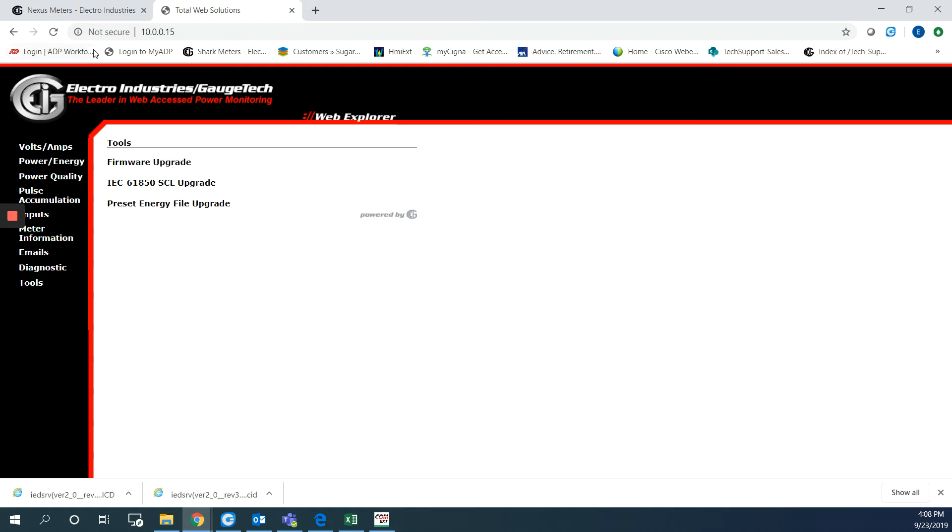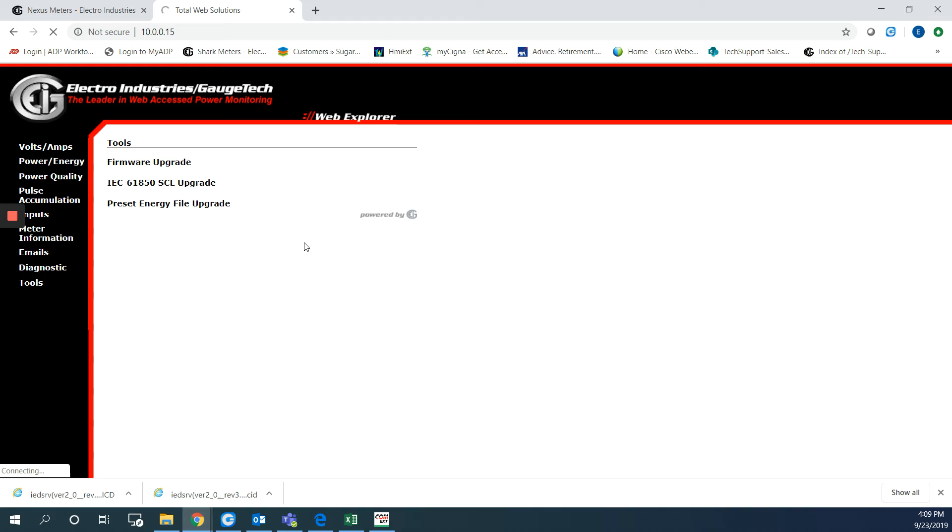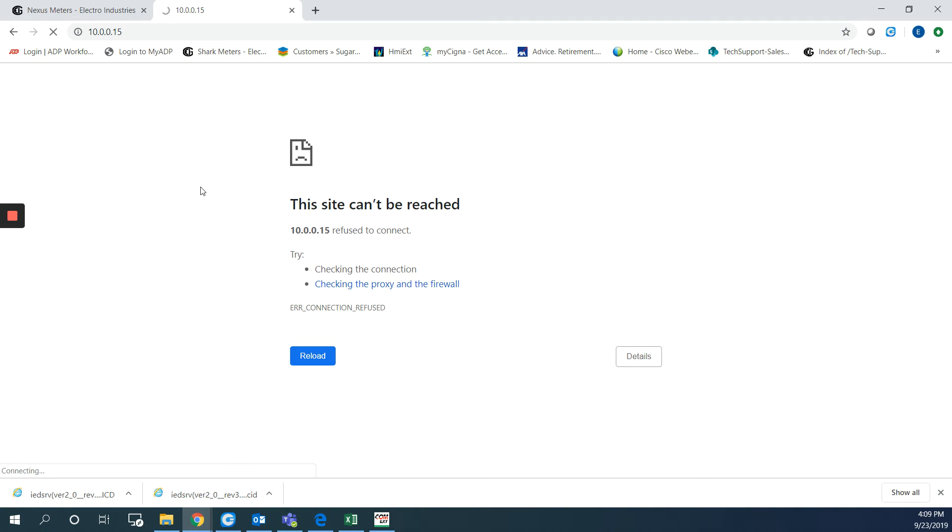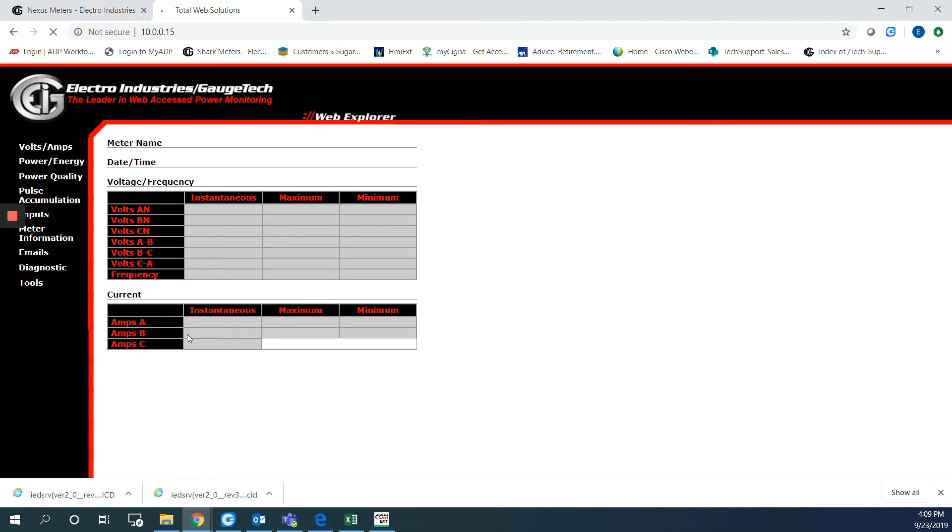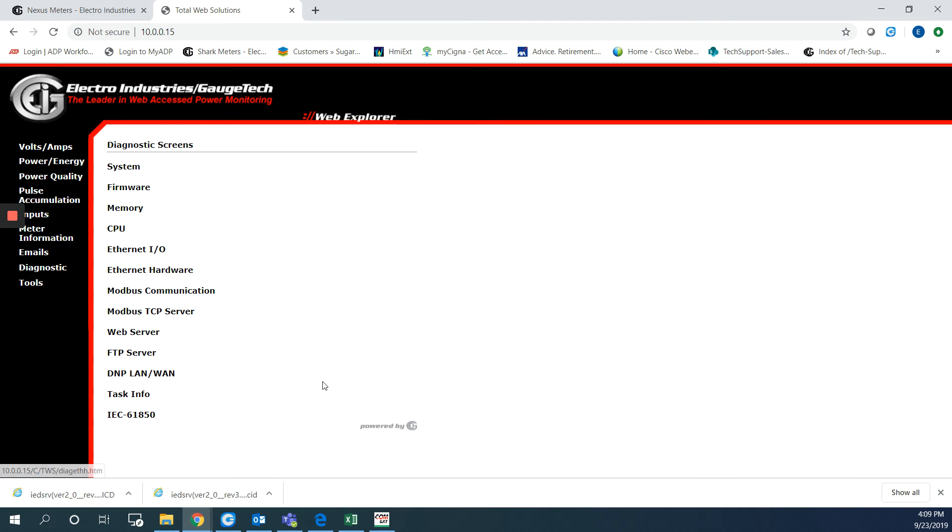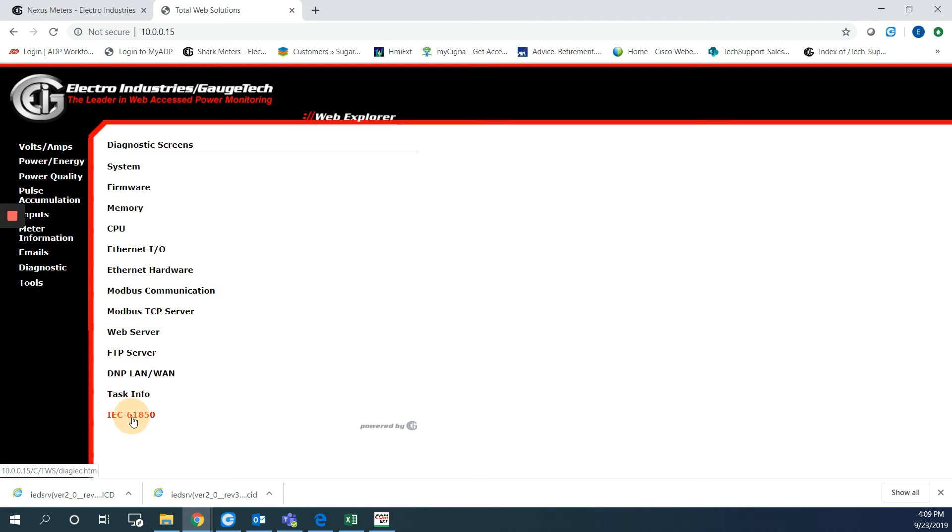If I go back to the home page here on the web page, it's still rebooting now. So once it's done here, I will go back to the home page and go to diagnostic. And from here I will choose the last option which is IEC 61850. So I can see that server successfully initialized. That means everything is fine.